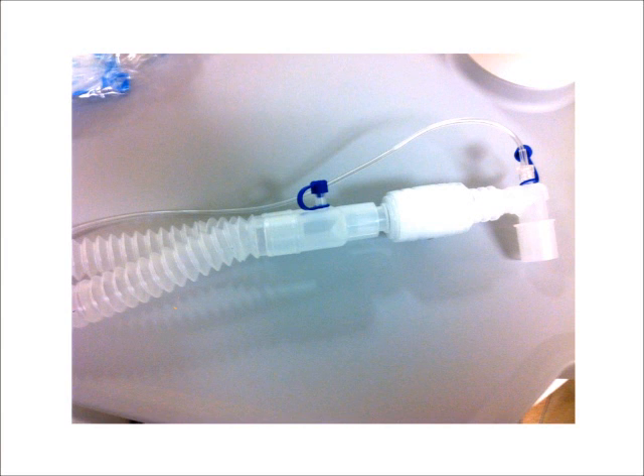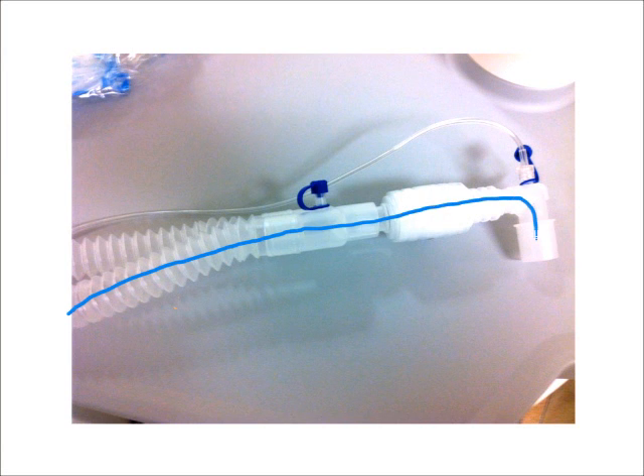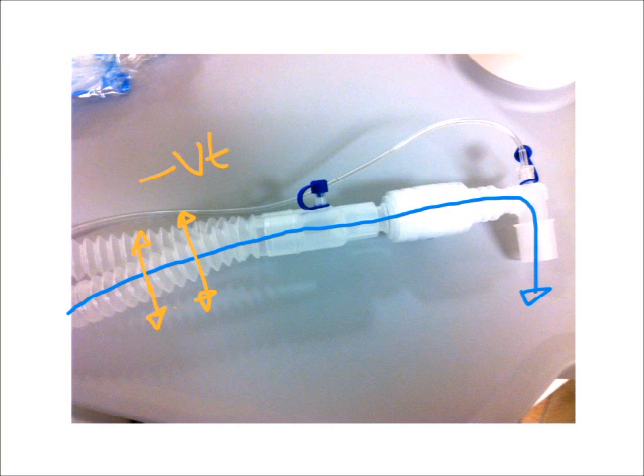So what happens is during a positive pressure breath, I am going to just draw a positive pressure breath going to the patient. Energy is also lost in the circuit. This energy is lost in the circuit because the circuit expands. This depends on how stiff the circuit is or how compliant the circuit is. And depending on how compliant the circuit is determines how much volume is lost in this circuit. And this volume does not go to the patient at all.